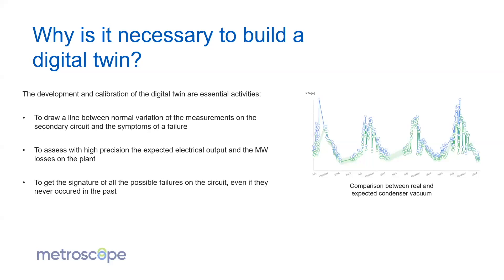But the digital twin is the key element in Metroscope's added value. The development and calibration of the digital twin to match the power plant is really what draws the line between normal variation of measurements and the symptom of a failure. Here on the right, the first output of Metroscope: in blue you have the actual measurement of the plant, and in green the expected behavior computed by our digital twin. You can see that, for instance, at the very beginning there is a gap between the measurement and the expected value, and Metroscope is able to analyze these gaps across multiple sensors and go back to the root cause.